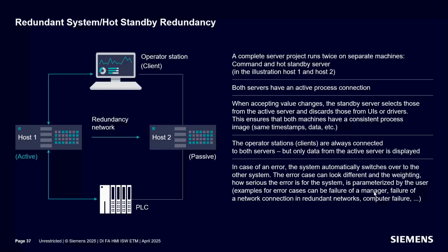And when there is a switchover situation, because there is a partial failure of one of the 2 machines, the switchover is of course seamless for the user interfaces and for the other processes. Seamless means the switchover happens in some milliseconds. Of course, typically after the switchover you do some additional things like a general query and so on, and there is then some work for the system to do afterwards, but the switch is really fast.